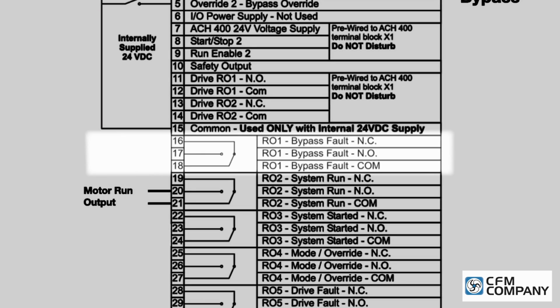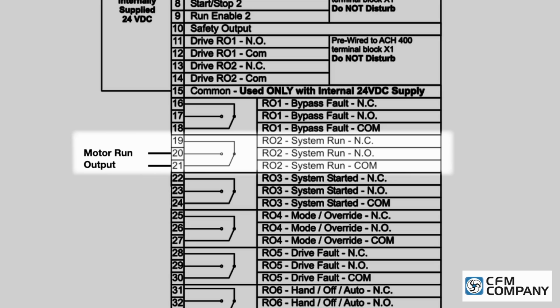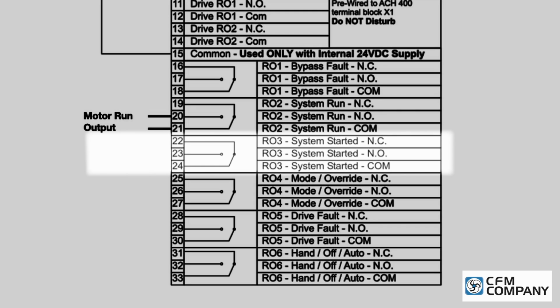Relay 1, terminals 16, 17, and 18 is the bypass fault relay. This relay is energized when the bypass is not in fault and the overload protection is reset. Relay 2, terminals 19, 20, and 21 is the system run relay. This relay is energized when the motor is powered either by the drive or the bypass. Relay 3, terminals 22, 23, and 24 is the system started relay. 3 conditions must exist to energize this relay. A start command must be present, the safety interlock input must be made, and there must be no active faults in the system. The system started relay is ideal for damper actuator control.